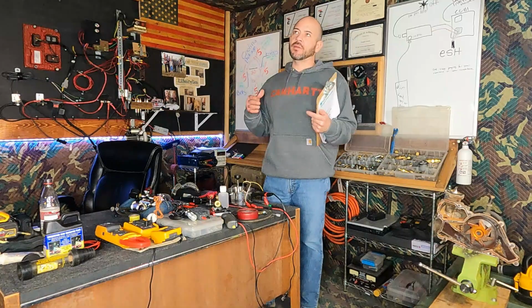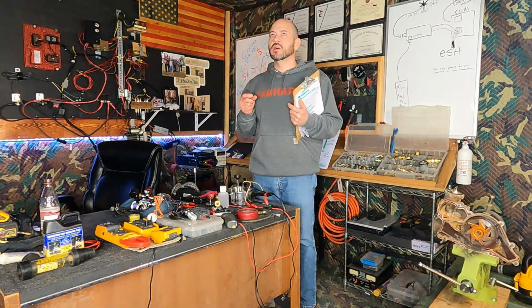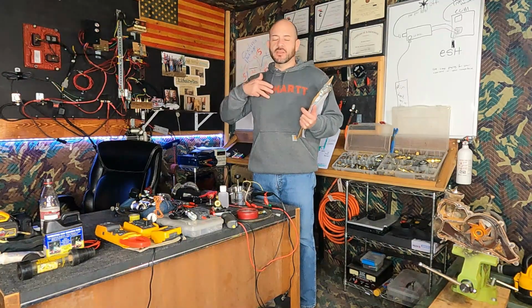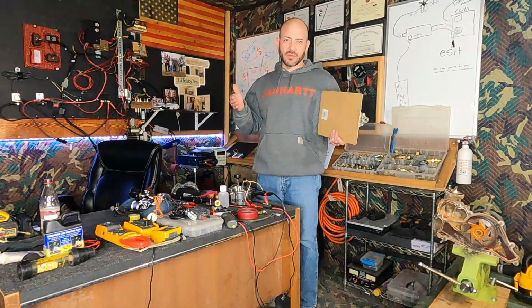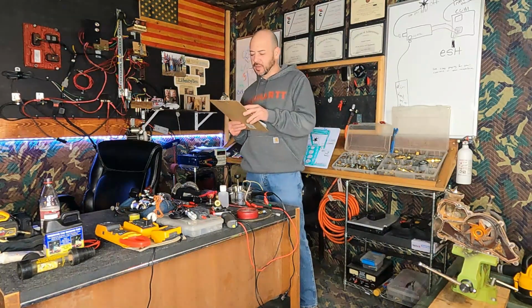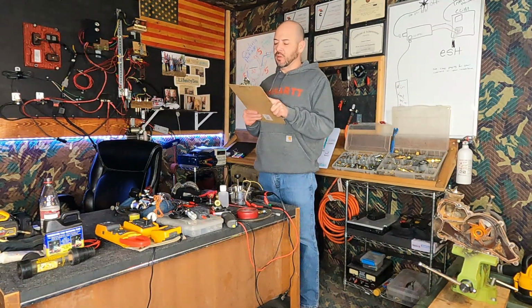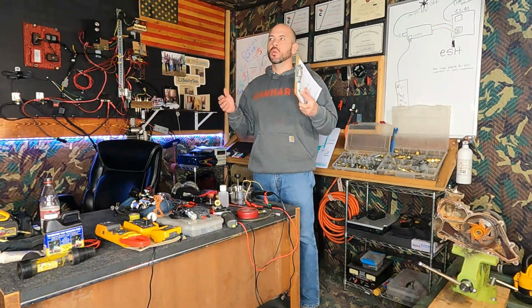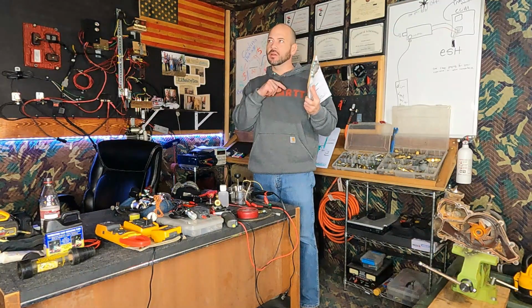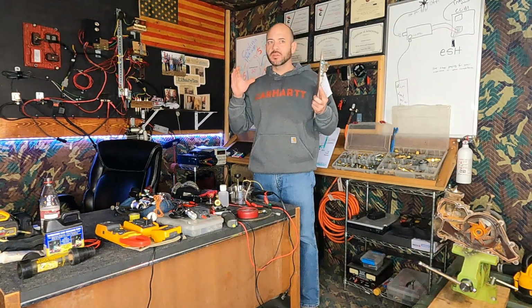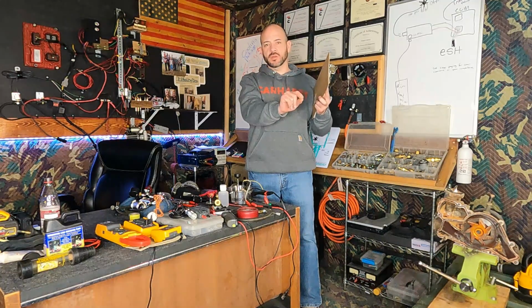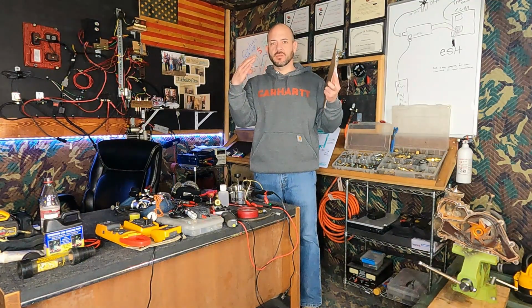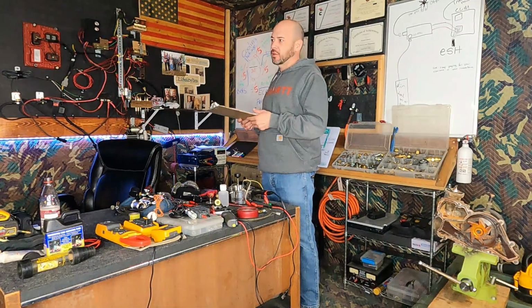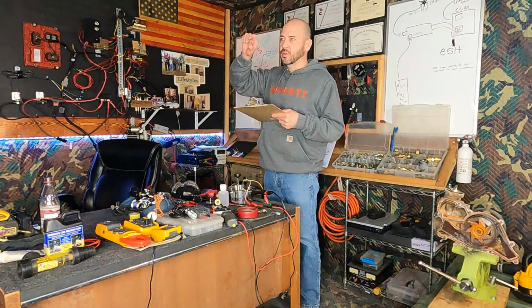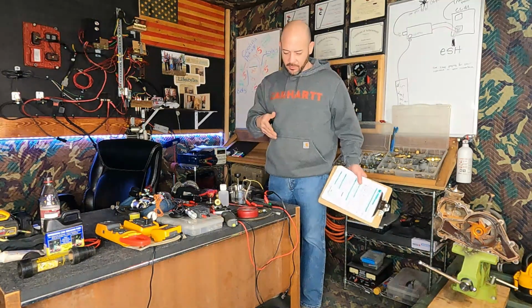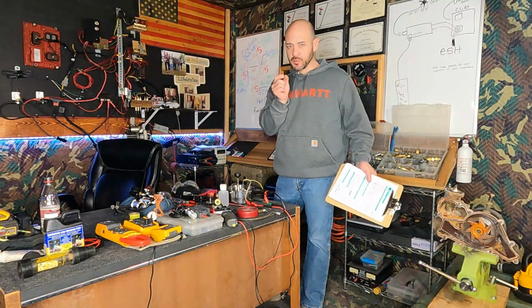The only other thing I've found to see if you have a busted cooler is a test plate kit that they sell. It's kind of expensive, and it requires compressed air and a few fittings, but essentially it does the same thing. Remember too that oil coolers, any cooler, will split, especially EGR coolers, and I'll talk about that in a second, when there's a huge temperature differential between the fluid going through the tube and the external temperature of the fluid outside of that tube. There has to be a certain amount of temperature difference where it doesn't exceed that, or those bundles or those tubes will split.